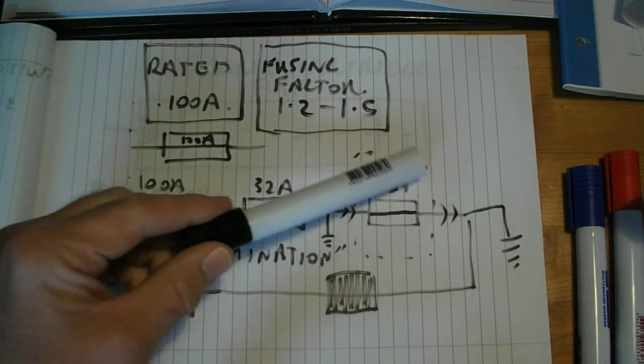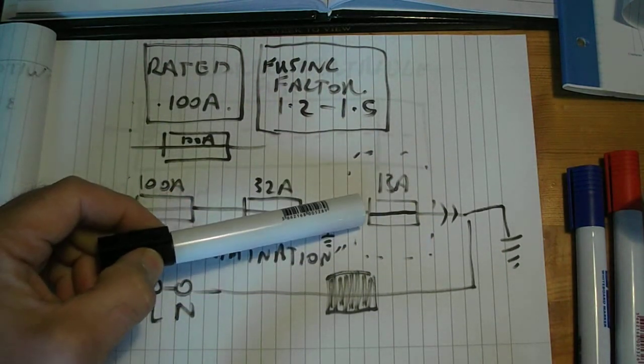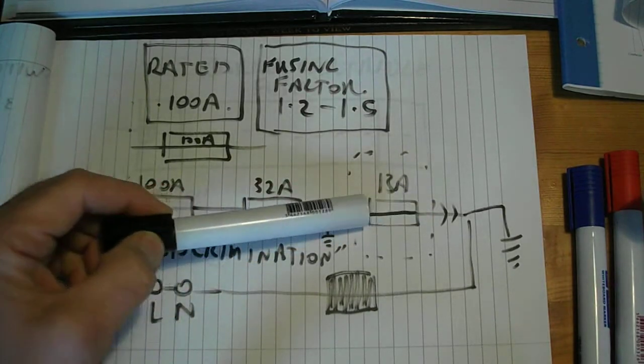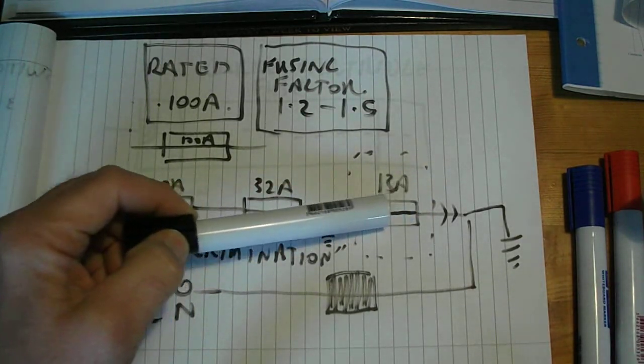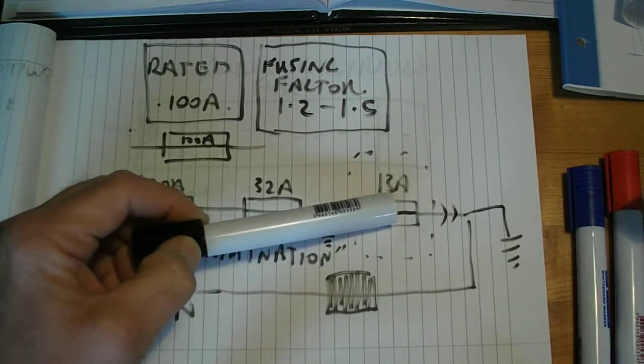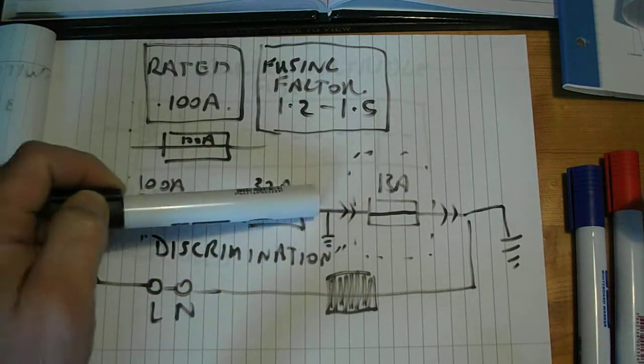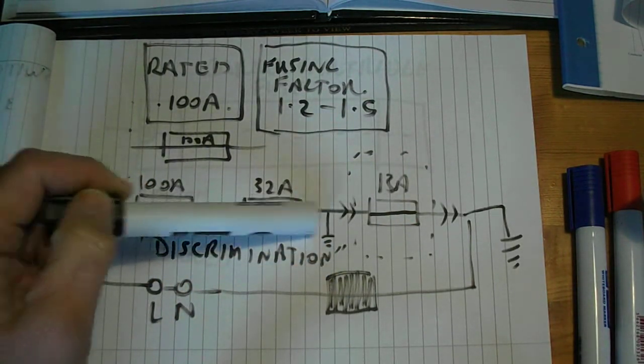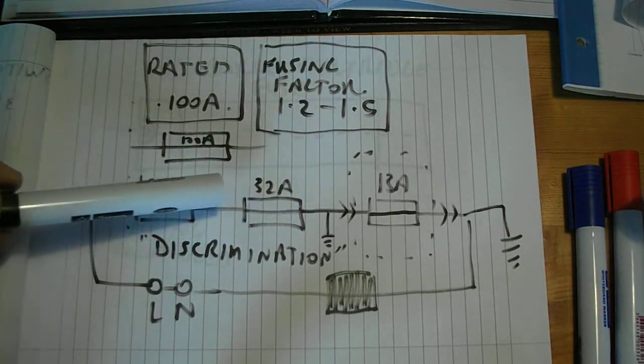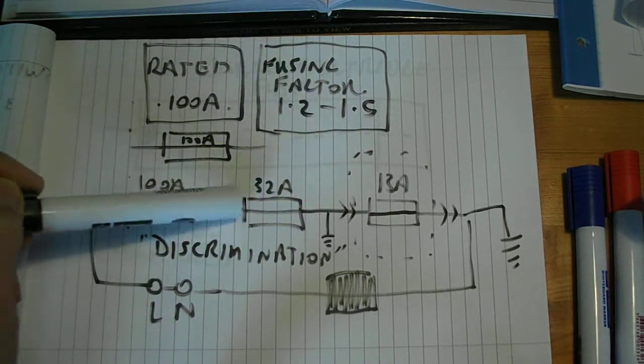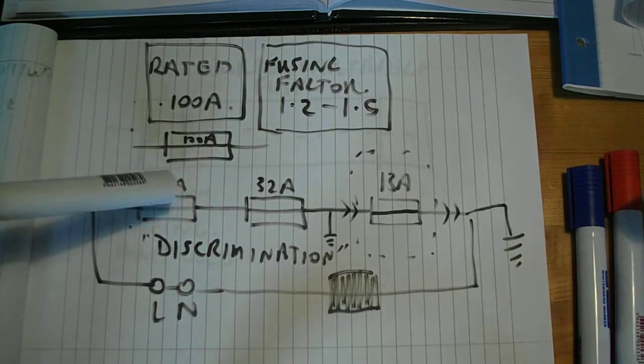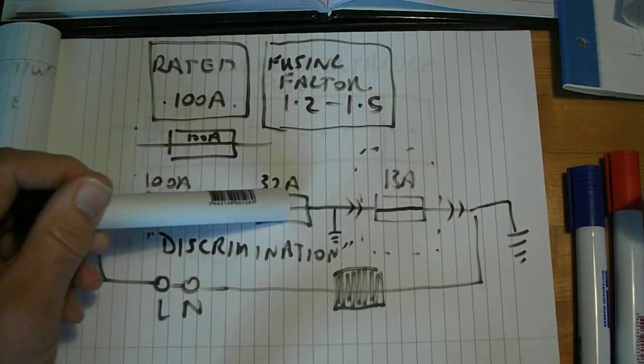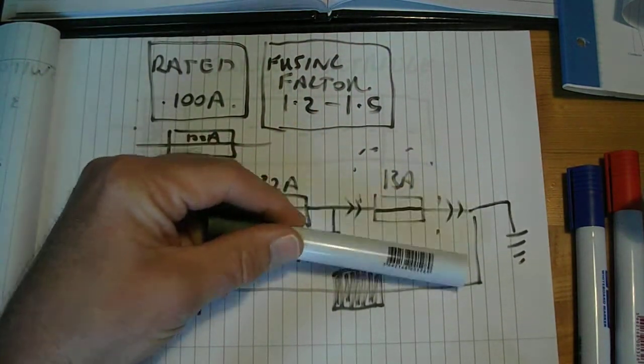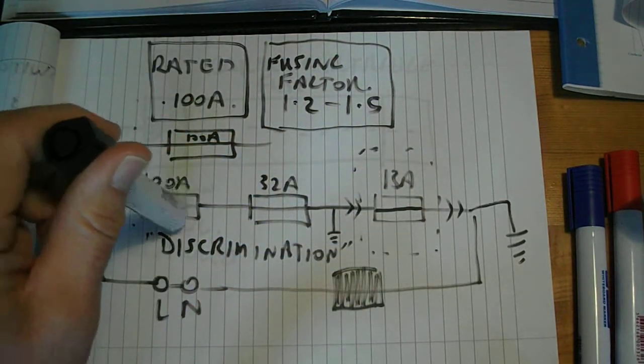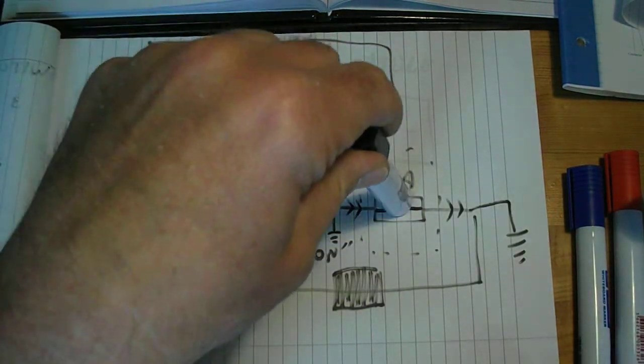Occasionally customers try to buck the system by putting a nail or safety pin across the fuse link if they don't have the right fuse, and they could do the same in the circuit board. If that's done, an awful lot of current has to flow through the whole system to make the cutout fuse blow, and that could actually cause a fire in the property. So discrimination is when the fuse nearest the fault blows first.